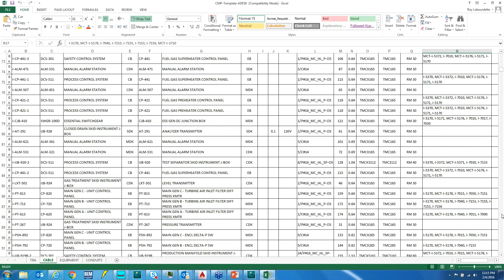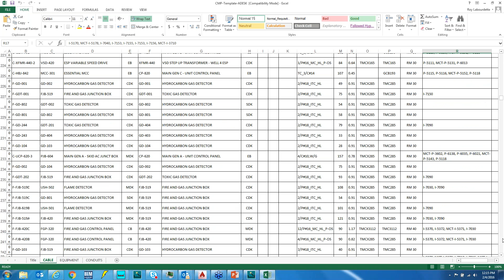It's also going to give me the cable size, the length as it's routed through the raceway, plus the additional route length that I can control in my project setup, and the OD of the cable. It also tells me the cable gland, whether it's a sealing gland or a non-sealing gland, and the multi-cable transit module block that would be required, so we can get a takeoff also on our MCTs. And it gives me the detailed route in the sequence that cable would be installed in the raceway system. So there's all of my cables, and again, it's in an Excel format, and it is completely customizable to meet your client or project or company standards.